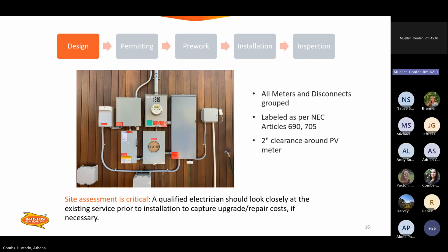Here's an example of a good wall. You've got your PV meter and your revenue meter, and they're grouped, and there's 2 inches around both of them. It is labeled per code. And yeah, the disconnect is grouped. And on this wall, everything is good to go. A qualified electrician should look closely at this service too prior to the installation, just to make sure that you're not missing anything and you don't install a system that has other issues with the existing service.